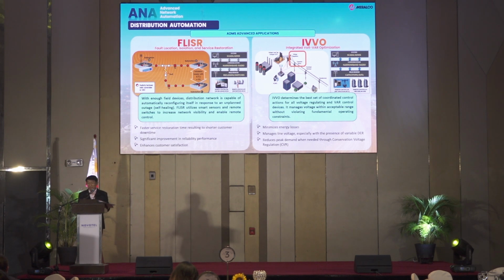First is FLISR, which we call fault location, isolation, and service restoration, wherein all the devices, the recloser, the line switches, are automatically reconfigured in response to an unplanned outage. It is a centralized approach through SCADA and ADMS, wherein it automatically isolates and reconfigures segments of the distribution feeders using sensors, control switches, and a robust communication system.